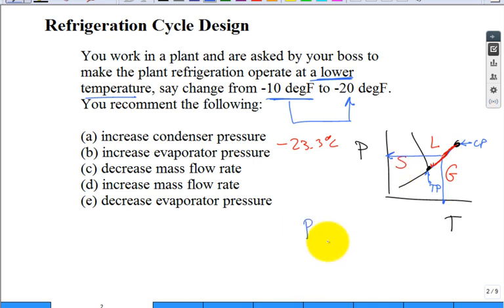So, this would be knowing, given a temperature, I can get P-SAT as a function of temperature. Or turn it around, and given a pressure, I can get saturation temperature. So, T-SAT as a function of pressure. So if I want to make it colder, the trend in the slope of this line is such that, what do I do with the pressure? Go lower. Go lower. You need a lower evaporator pressure.